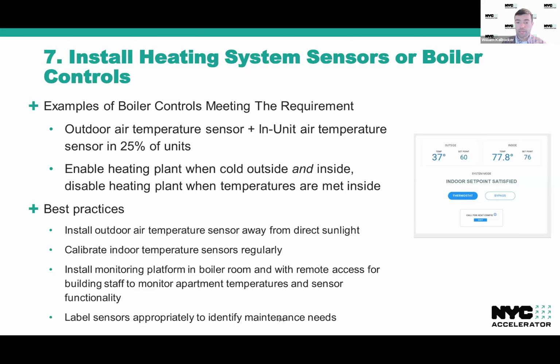It's recommended to install that air temperature sensor in the outdoor environment out of direct sunlight so that it's getting a proper read on the air temperature and not being falsely heated up by direct sunlight. It's really important to calibrate indoor temperature sensors regularly so that they're giving good data back to the boiler. And installing a monitoring platform with remote access for building staff and ownership is definitely a great idea. Building operators love it because they don't have to necessarily be on site to know exactly what's going on. And it's always a good idea to label sensors appropriately for maintenance requirements.